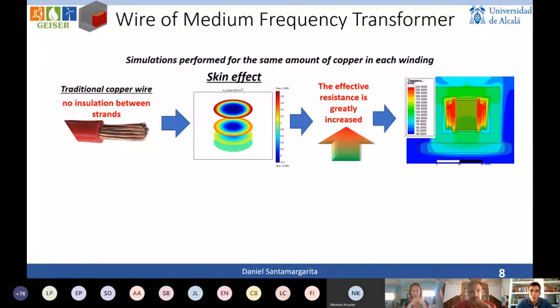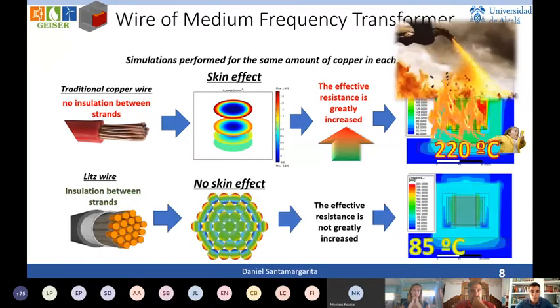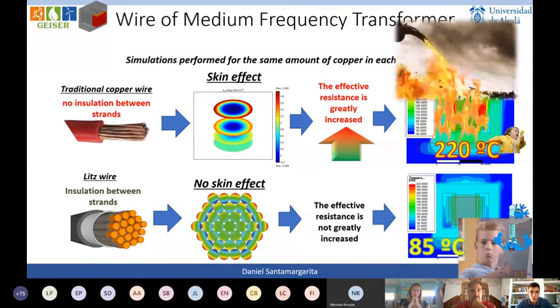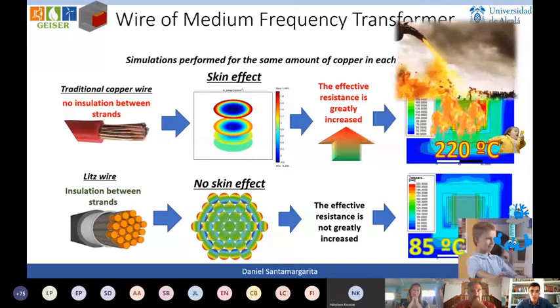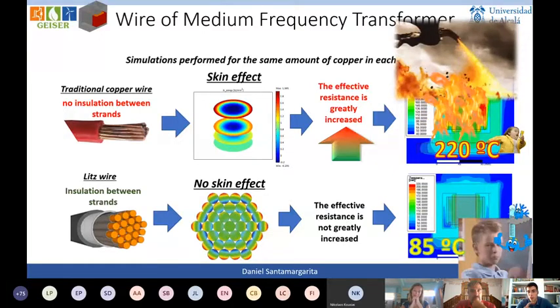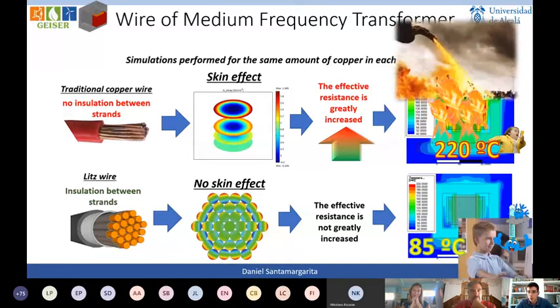If we design a medium frequency transformer with the same power and voltage as a traditional transformer, we might assume we can use the same wires since it's the same current. The problem is that at medium frequency, we get a skin effect: the current travels along the surface of the cable, increasing its effective resistance, so the transformer reaches very high temperatures. Instead, a good solution is to use a litz wire with insulation between strands, which avoids the skin effect and keeps the transformer at a good temperature.